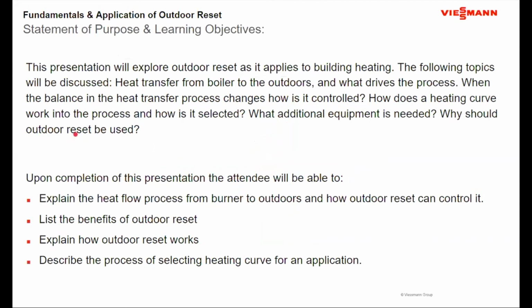So, we covered a lot of ground during the course of this presentation. We explained the heat flow process from the burner to outdoors and how outdoor reset can control it. And it's really about 3 transfers: across the heat exchanger in the boiler, across the heat emitter in the building space, and across the wall of the building, and how we can balance them with outdoor reset. We talked about the benefits of it, how outdoor reset works, and we talked about selecting a heating curve.